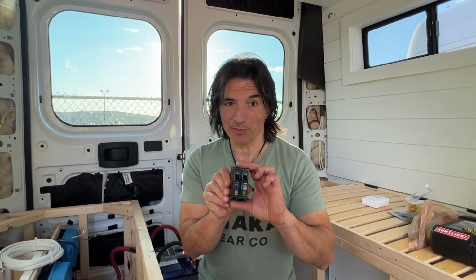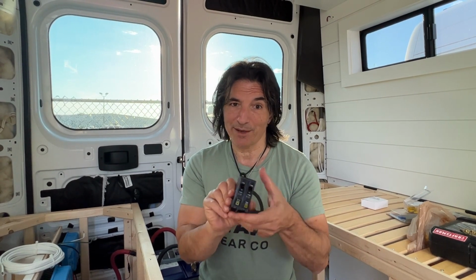So it'll be two circuits. We'll have a 15 amp breaker on one, and that's going to be mainly to power our hot water heater. The other one will have a 20 amp breaker, and that one is mainly to power our induction cooktop. And each of them will probably have an AC outlet or two tied to that one as well. So here we've got our two circuit breakers that we're going to use. We've got a 15 amp and a 20 amp.